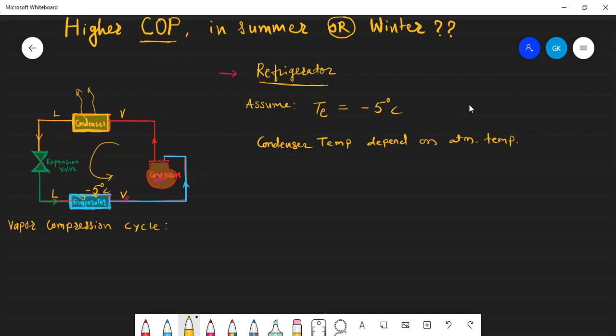than the atmospheric. Now we are comparing summer and winter. Assume that the summer temperature, which in the Indian subcontinent we can consider to be 35 degrees Celsius. So for summer, what should be the condenser temperature? It must be greater than 35. As a thumb rule, we consider at least 5 degrees Celsius temperature difference, delta T. So condenser temperature for summer may be around 40 degrees Celsius. Similarly, in winter, let us consider the average winter temperature is 20 degrees Celsius. So for winter, the condenser temperature becomes plus 5, that is 25 degrees Celsius.